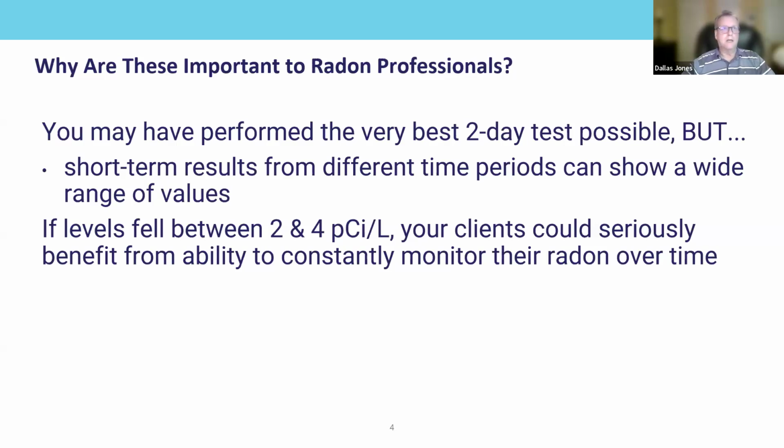It wasn't that cold, and it also appeared from what I could see on a FaceTime conversation that she may very well have had some leaky return plenum down in the walkout basement of her home that could have been lowering the differential pressure in that basement with reference to the soil. So when that air handler kicked on, it was actually sucking air into the leaks in the return, which was then sucking more air from the soil through the cracks in the slab, around the slab and foundation openings. So every night it would go up and every day it would go down.